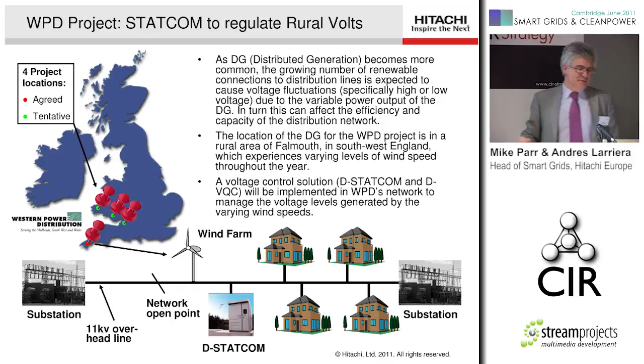This slide provides a few more details on the project. It's in two parts. The first part is simply to prove that the D-STATCOM will regulate HV volts, and by implication, LV volts too. The second part is to install three StatComs on a network, probably in South Wales, including a voltage quality controller. That will communicate with the StatComs and control them to a certain extent. It will also control the on-load tap changers in the primary subs, and control auto transformers, if you have them - electromechanical devices some DNOs use to try and regulate line voltages on the 11 kV network.